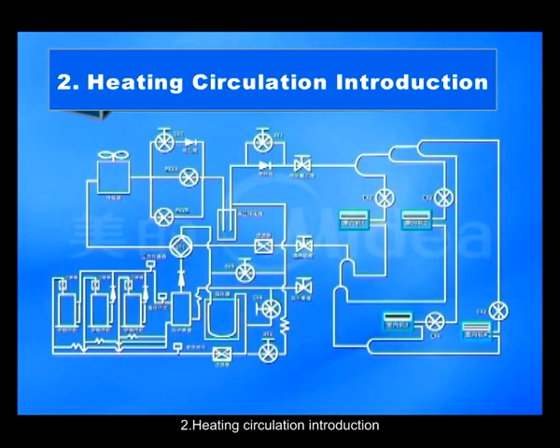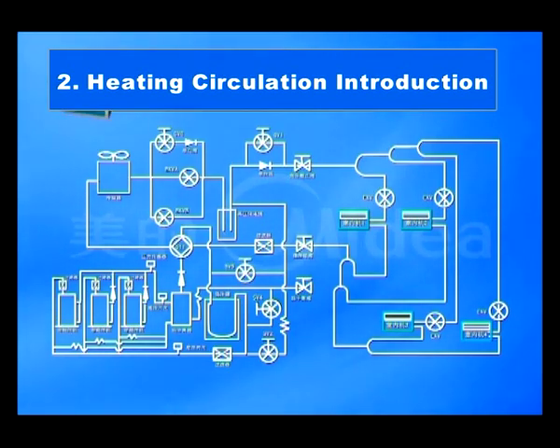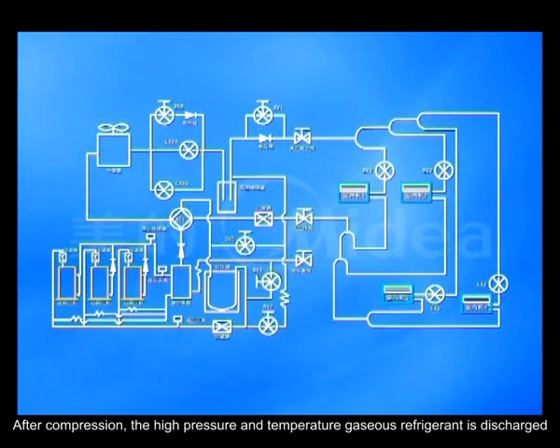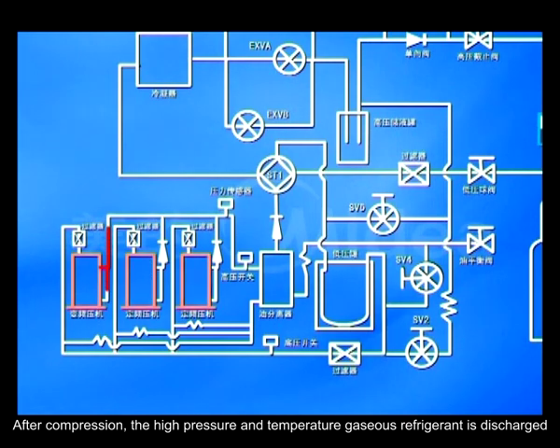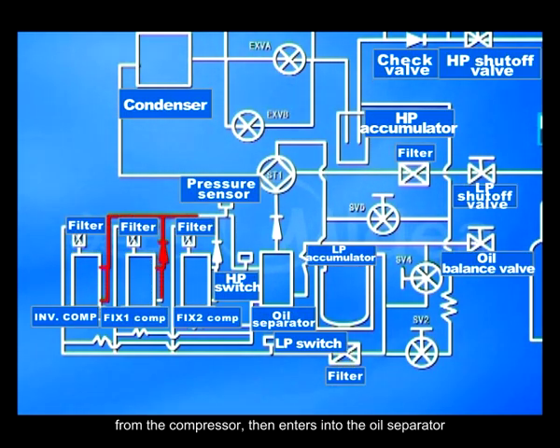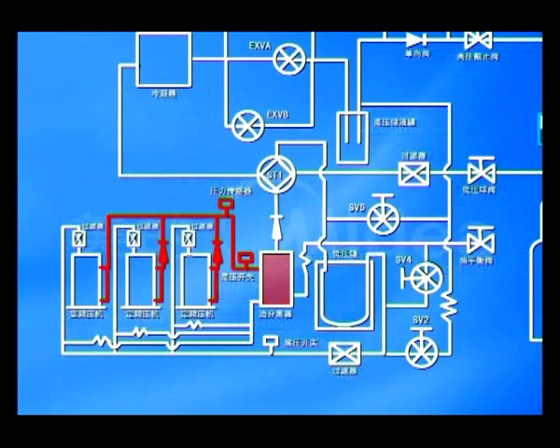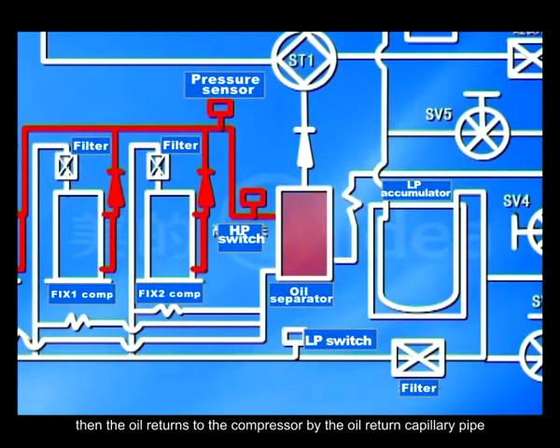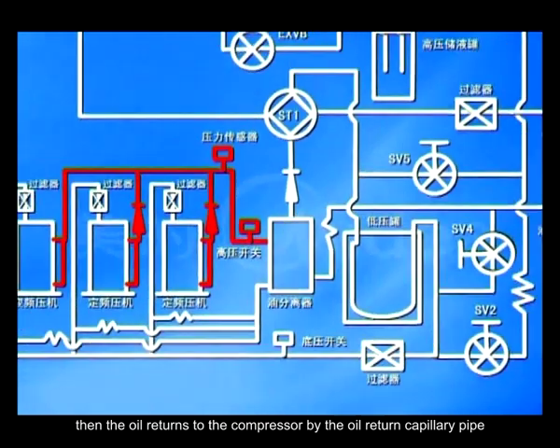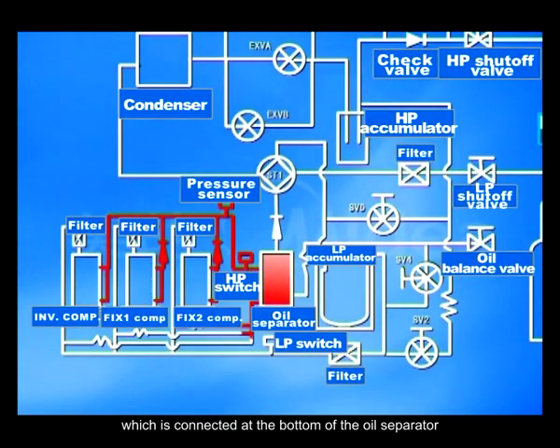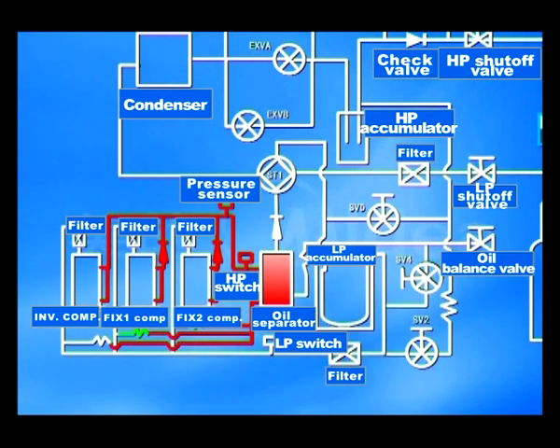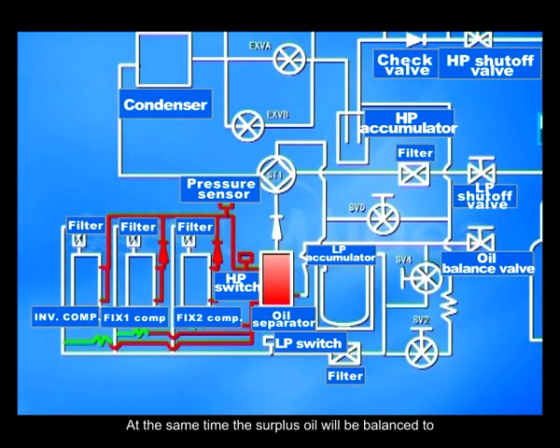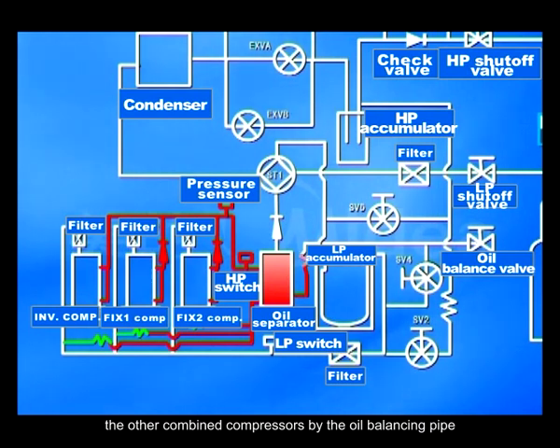Two, heating circulation introduction. After compression, the high-pressure and high-temperature gaseous refrigerant is discharged from the compressor, then enters the oil separator. Oil is separated from the refrigerant by the oil separator. Then, the oil returns to the compressor by the oil return capillary pipe, which is connected at the bottom of the oil separator. At the same time, the surplus oil will be balanced to the other combined compressors by the oil balancing pipe.